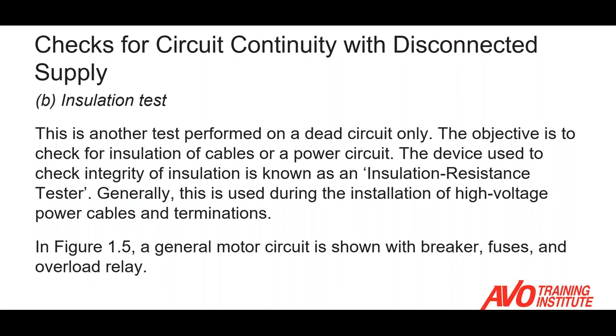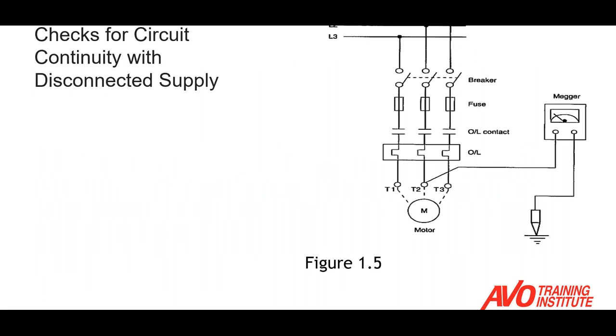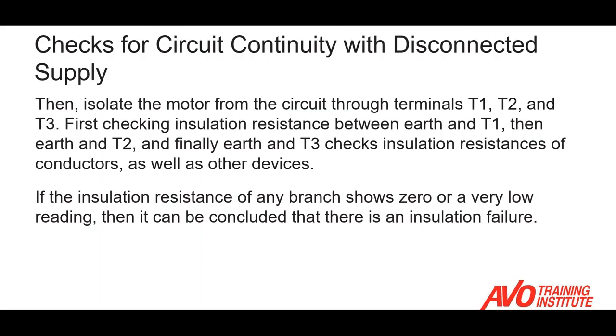Another check associated with continuity is the insulation test, which also needs to be performed on a de-energized circuit. The whole objective is to check the integrity of the insulation of the power cables and control wiring — this is known as an insulation resistance test. Looking at this slide, we have a typical power circuit for a three-phase motor with the overcurrent device isolated from the circuit as well as the motor, allowing us to check the integrity of each phase going to that motor. We want to check from terminal T1 and T2 to ground to make sure we don't have a path to earth.